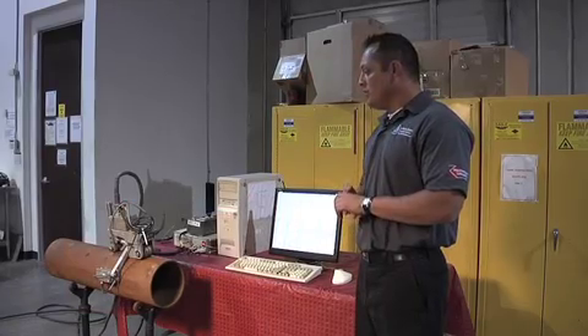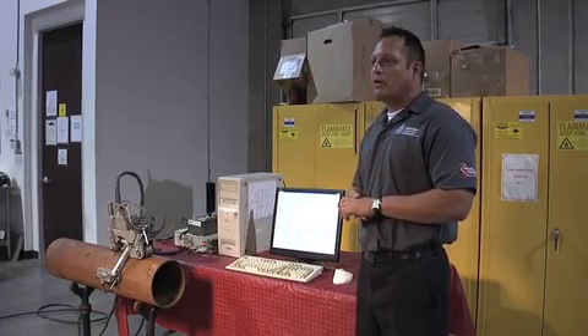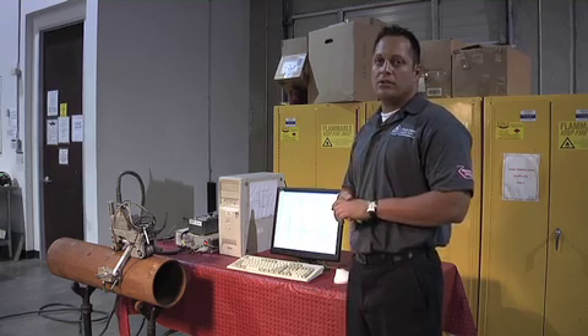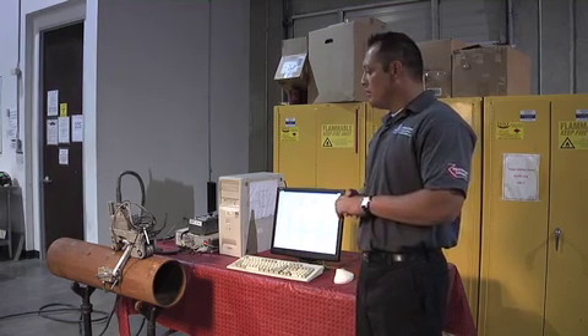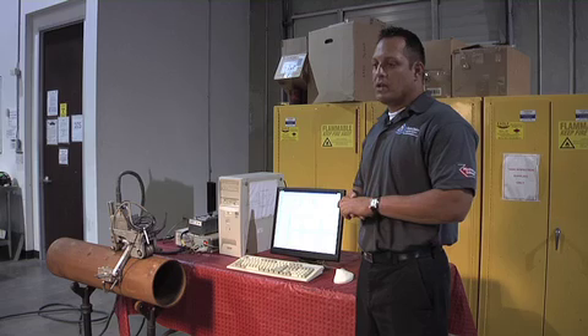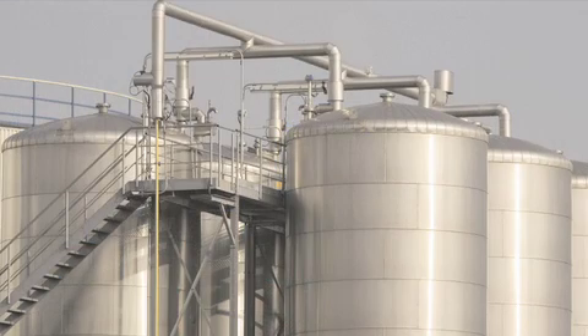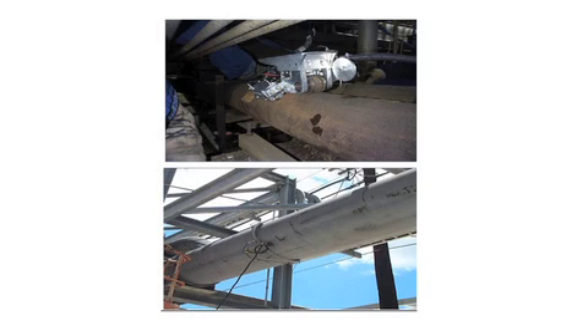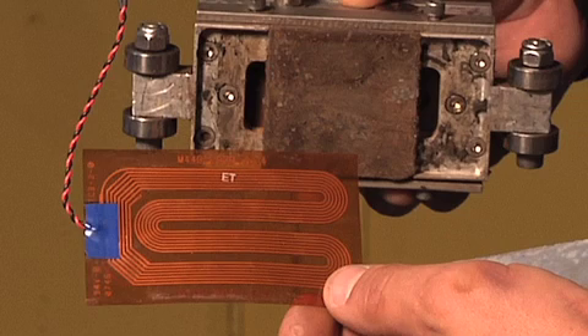It's generally used for pipe inspection, your dock lines, your transfer lines, your tank farm lines, lines that are not easily accessible. We've also used EMAT for tank bottom floor inspection that exceeds your typical MFL inspection techniques. One of the main benefits of EMAT is you can inspect the full volume of the pipe itself without having access to the area. And the way EMAT works, it's a very low frequency and it uses a meander coil.